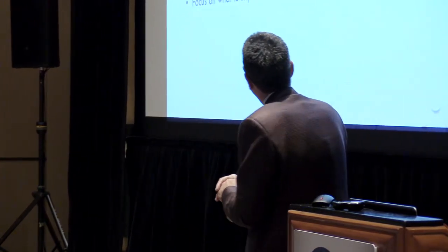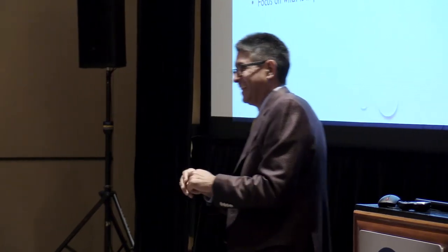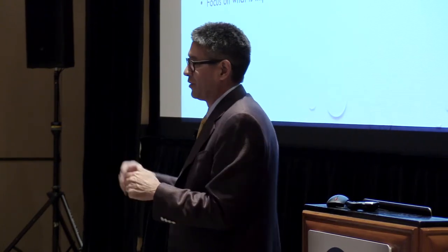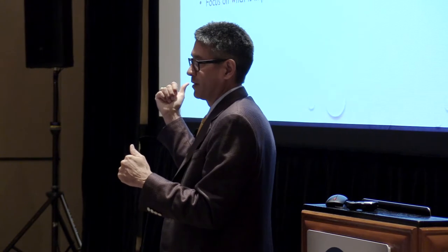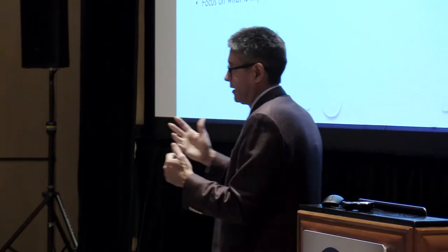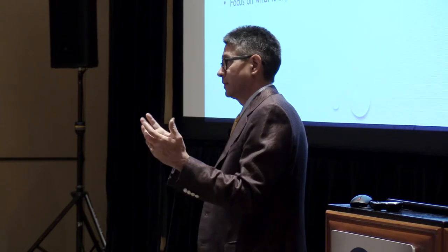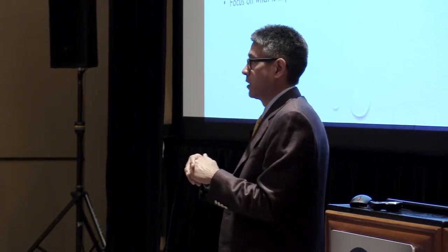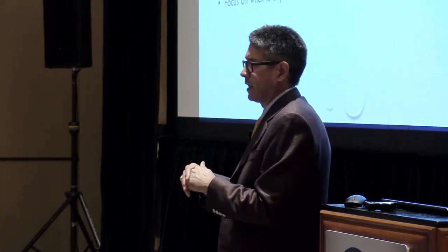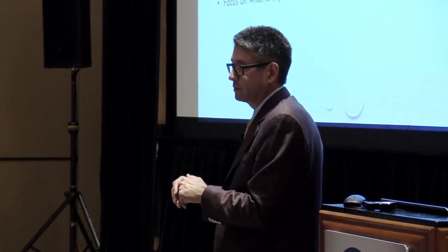Reverse return still does great. Tried and true, it's the first thing value engineered out of every job. But I'd rather go reverse return than a bunch of pressure independent control valves or a bunch of flow technology valves that are trying to give me flow back on a reheat system. I would venture a guess that a reverse return system would be less expensive to do and a heck of a lot more efficient too. So don't ever shy away from a reverse return system. There's a lot of customers, I laugh, who have it specified as their standard for all their buildings, but it's always the first thing value engineered out.